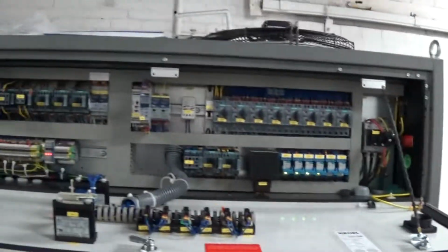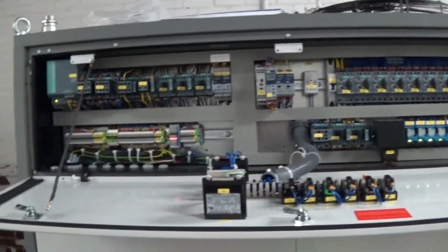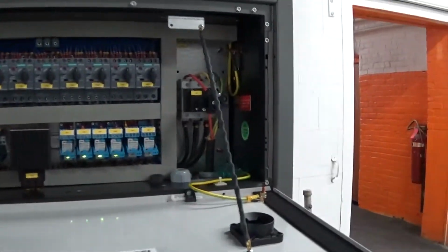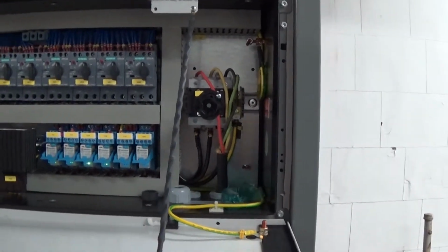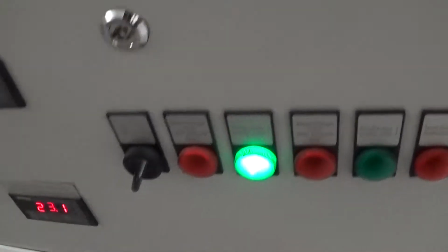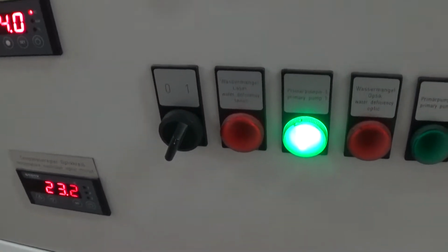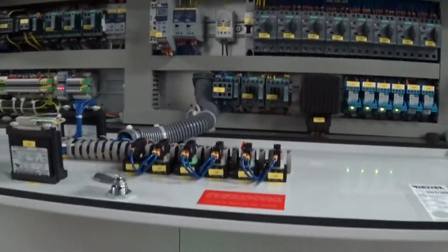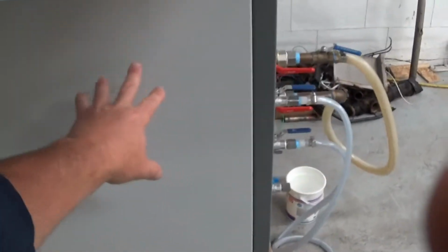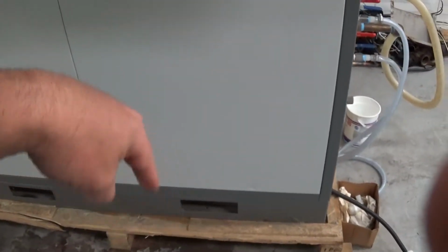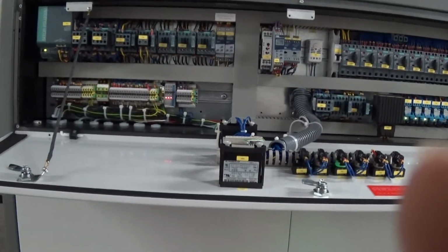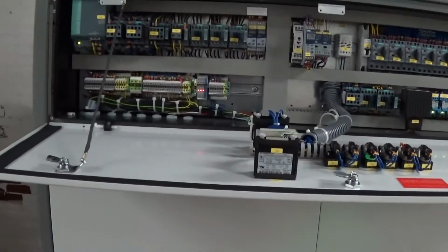When you first start, when you are doing piping and powering this unit up, you want to check for pump rotation. The easiest way to do that is you bring power to the unit, make sure you have fluid in that primary tank, and with that on-off button here, you just toggle on and off really quickly, just for a second. That main power and the main pump will rotate. And if you recall, that main pump was behind this door here. Looking from the top, there should be a sticker on there. You want to make sure it's going clockwise, or however that sticker rotation is showing it. Do that with a flashlight. Sometimes you might need an extra helper. I was able to do it myself.